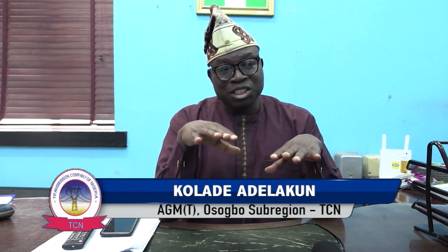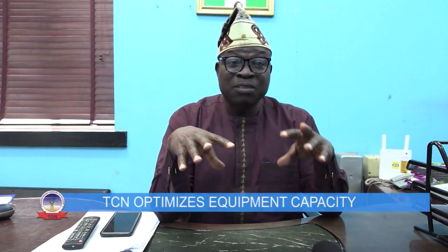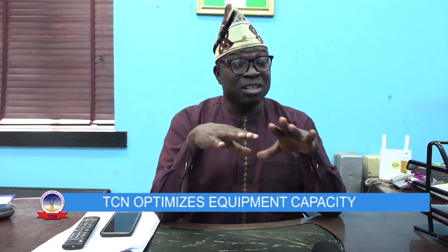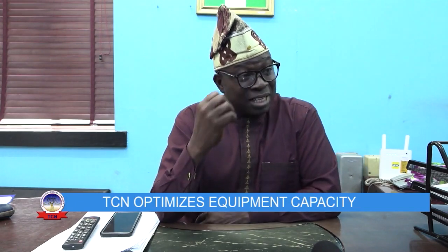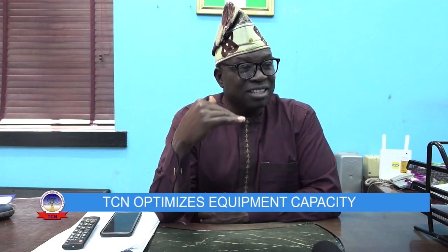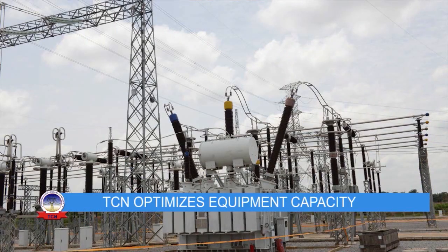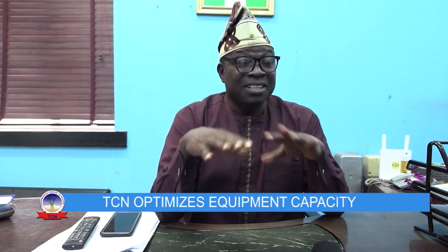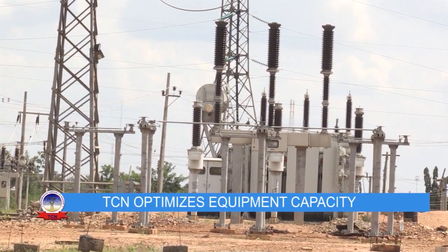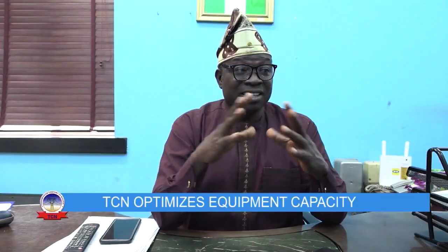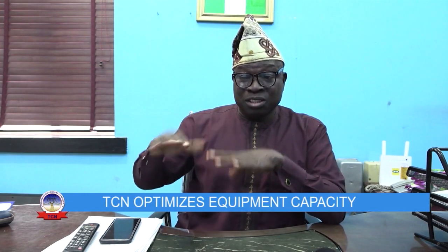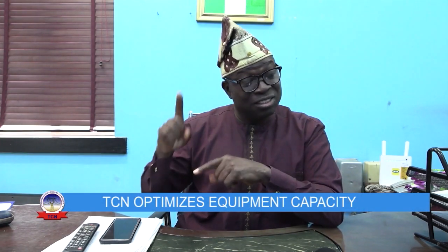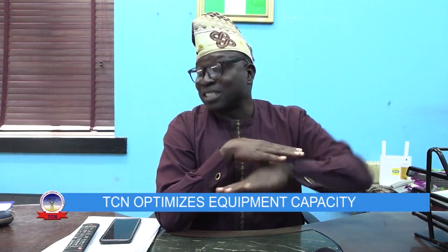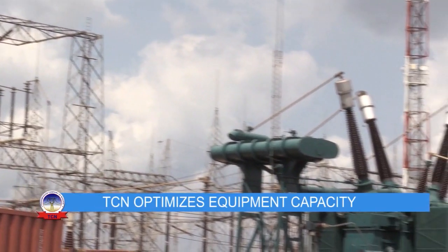If you have all these sludges, water, oxidation byproducts, cracking of the transformer oil, the transformer has been equipped with certain protective devices that will initiate its tripping off. You cannot have all those problems and the transformer is still healthy. In fact, if those protections are not there, the transformer can catch fire. Anything can happen. So, as long as all those sludges and water and byproducts are there, the protective device that has been designed to monitor its health is going to trigger it and it's going to trip off. So the transformer cannot even be in service. Any moment it senses this problem, it's going to trip off.